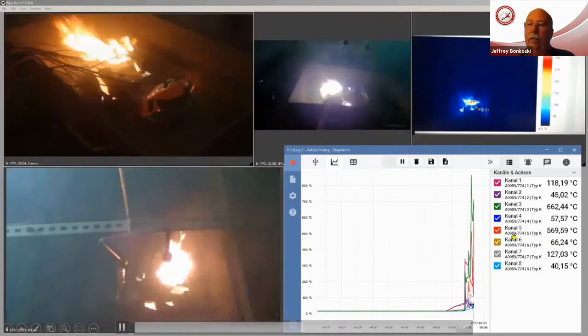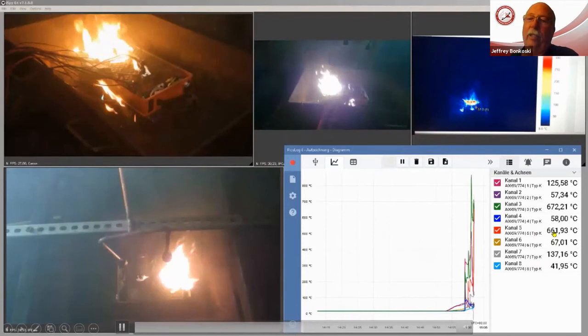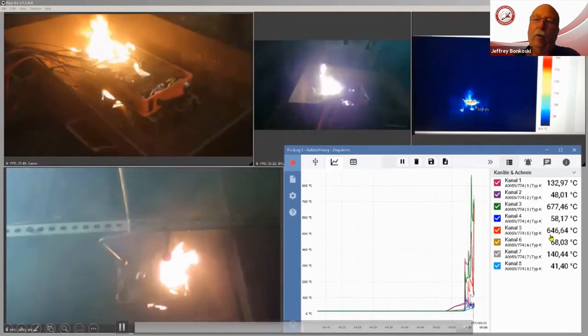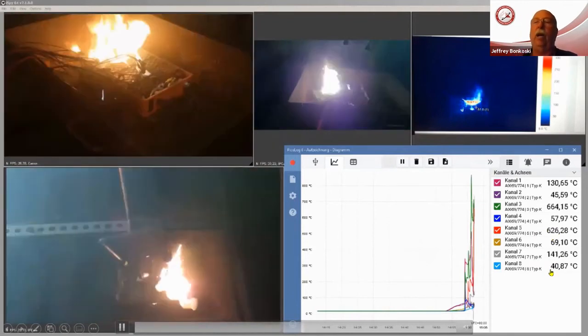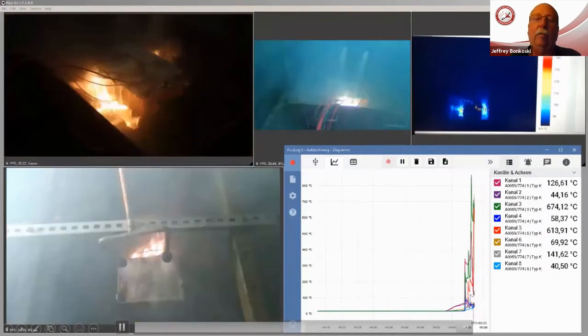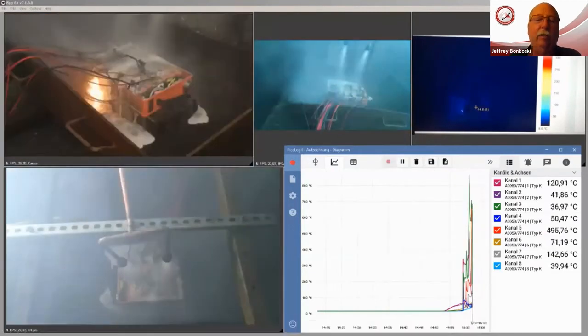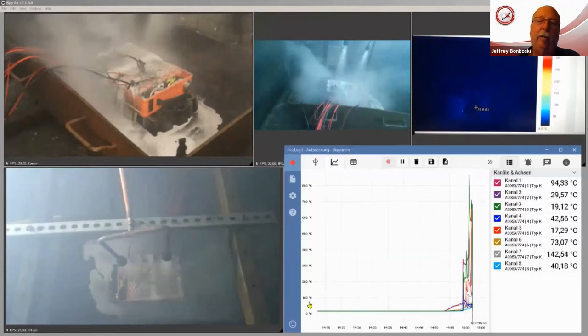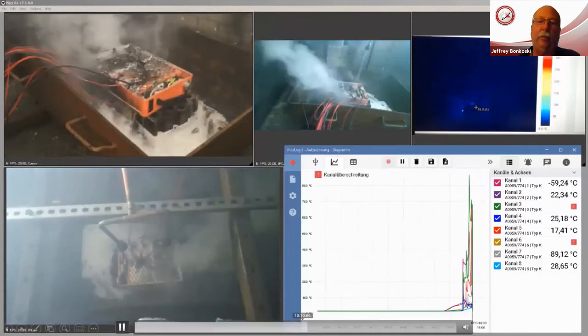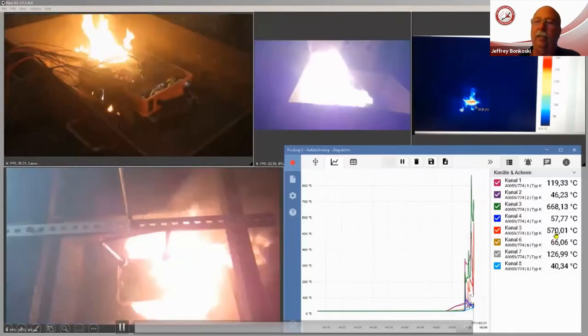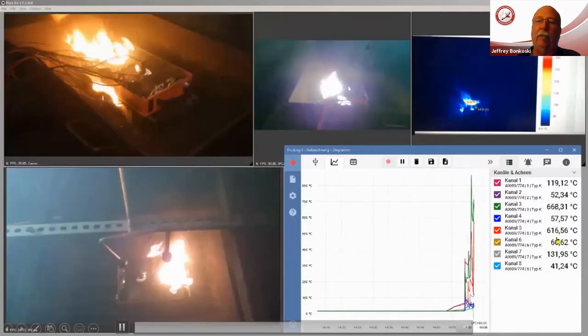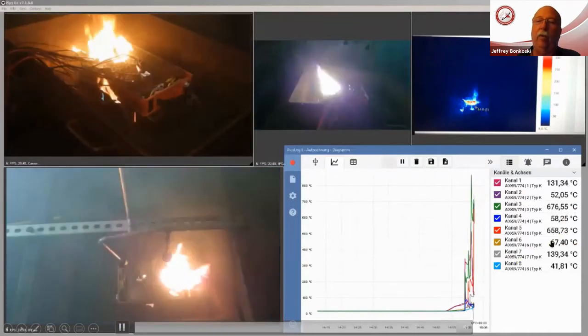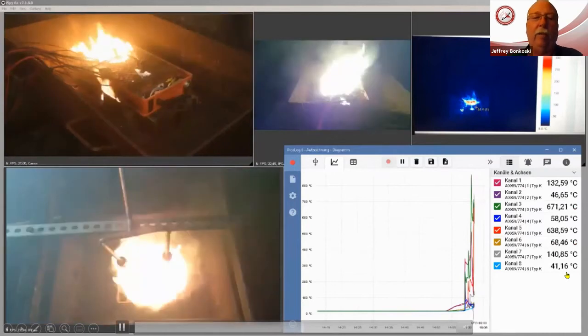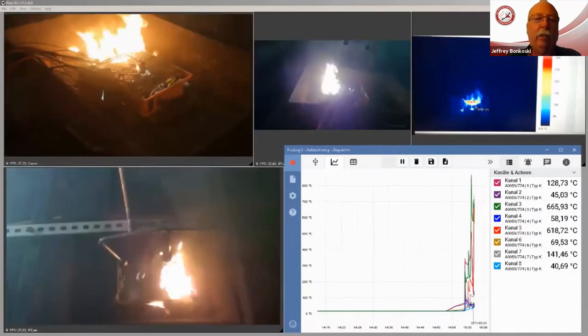On our number 5, you'll see how quickly those temperatures are starting to rise. I like to use the number 5 sensor because, as you can see, and I'm going to back it up, we were just at 500, 600, 700 degrees C, and watch how quickly those temperatures drop when F500 is discharged.